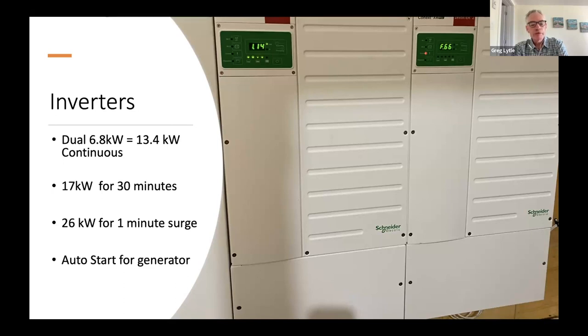We also have the inverter system set up so it auto starts the generator when the load exceeds what the inverter is going to output, which seldom happens in our case, or in the case where you don't have enough solar generation. The system monitors the state of charge of the batteries and will start the generator to recharge the batteries when required.